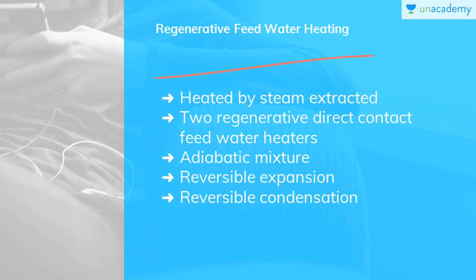Let's move on to regenerative feed water heating. The feed water enters the boiler at a temperature between stage 5 and 4S and is heated by steam extracted or bled from the intermediate stages of the turbine. The T-S and H-S diagrams with saturated steam at turbine inlet show two regenerative direct-contact feed water heaters. For 1 kg of steam at the turbine inlet, M1 kg of steam is extracted at pressure P2 to mix adiabatically in heater 1. The remaining steam expands reversibly to P3, when M2 kg steam is extracted to mix with (1 - M1 - M2) kg of feed water in heater 2. The remaining steam expands reversibly to the condenser pressure.